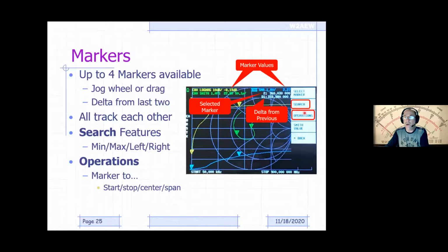Okay. And there's also operations you can do with the markers, meaning, let's say I've got a marker I've moved and say, I want that to be my new center frequency for my measurement. You can do a marker to center, and that'll readjust the center frequency of the VNA to be where that marker location is. So that's what the operations do. And then if you're looking at a curve on a Smith chart, you can choose what units the Smith chart is showing. In this case, channel 0, this green trace is a Smith chart trace that's on the circular axis here. And what it's showing, marker number 2 is sitting at 22.8 ohms and 50.1 picofarads right here. That's where that is on the Smith chart.